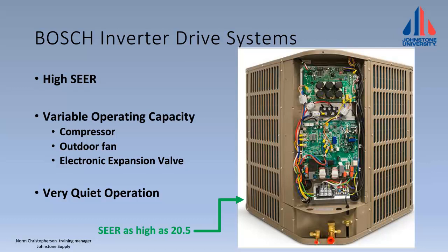After more than 50 years in the HVAC business, I've seen more than my share of industry changes. I'm an old school kind of guy. However, I have made it a personal objective not to lag behind in technology, but rather to embrace the technology. The days of electromechanical controls are fading fast. For example, there's no contactor in this heat pump outdoor condensing unit. Motor starters, contactors, start and run capacitors are not necessary. Don't let the onboard computer in this unit overwhelm you. Speaking from experience, I can tell you with confidence that this control system is not any more difficult than what we're already familiar with. In fact, in many ways, it is easier. And clearly, it's more efficient.